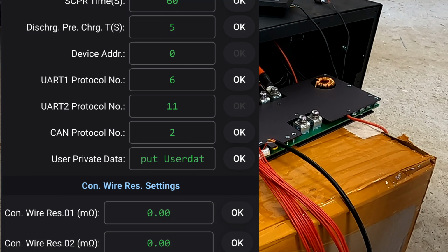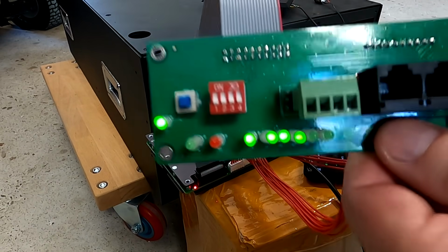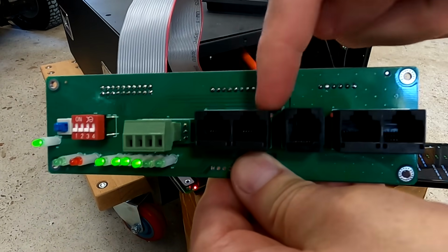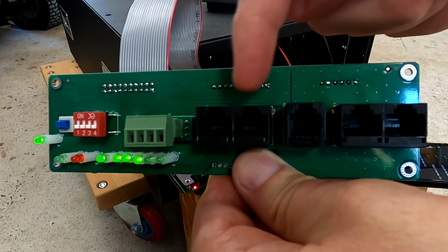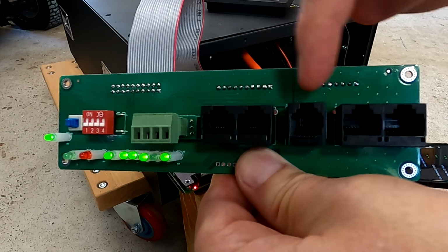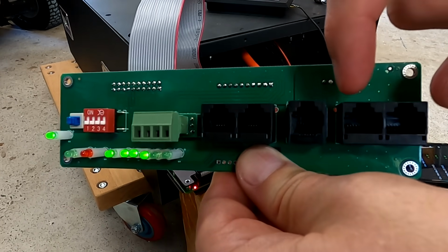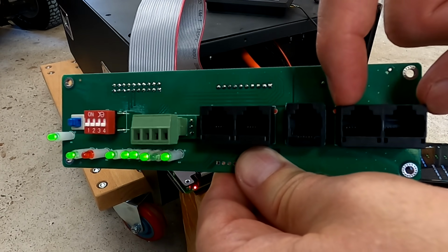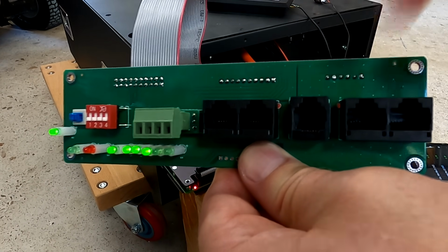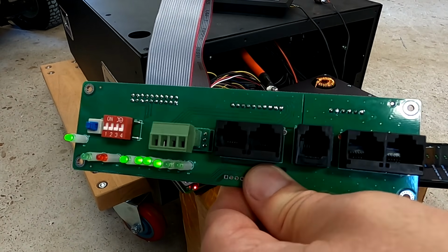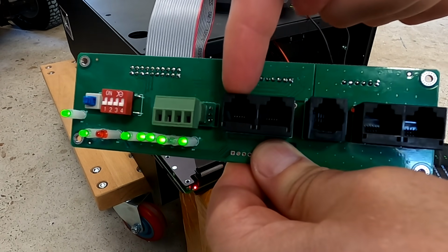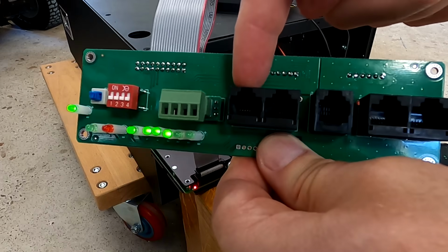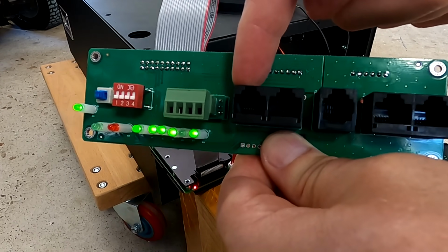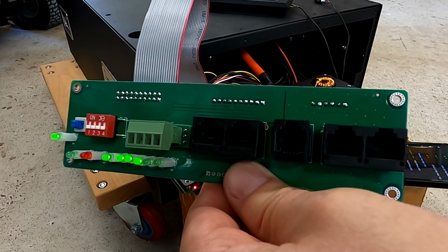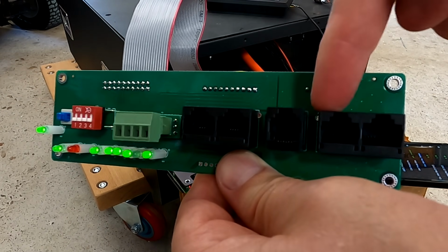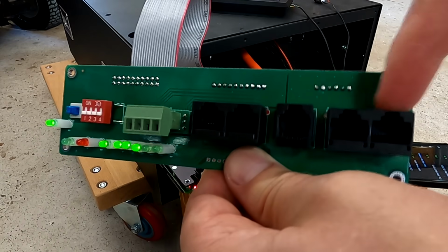And this is a bit confusing at the beginning. But having a look at the communication board, again, this is your inverter communication ports, RS485 and CAN, just for the inverter. Then we've got RS232, and then we've got 2 RS485 ports here on the right, which are for paralleling the BMS with other batteries. The UART1 setting is solely for this one port here, and you can set the protocol for your specific inverter talking RS485. The UART2 protocol is solely for these 2 ports here. This is for the internal communication.